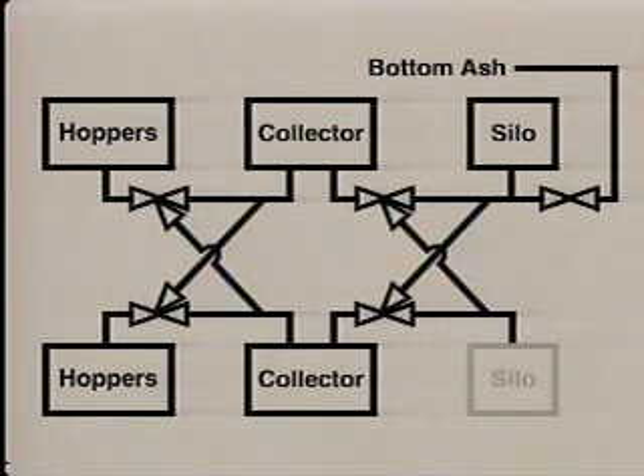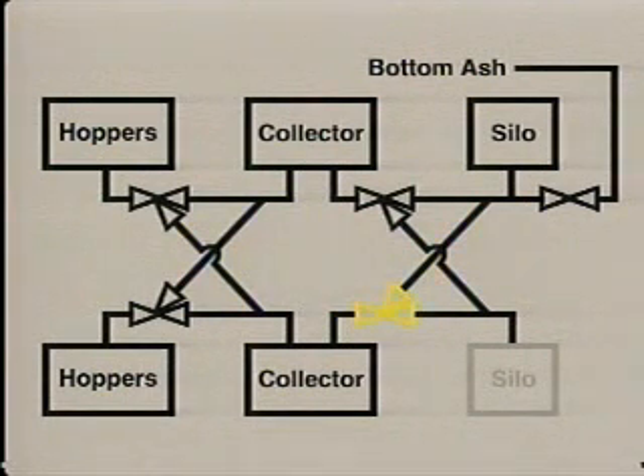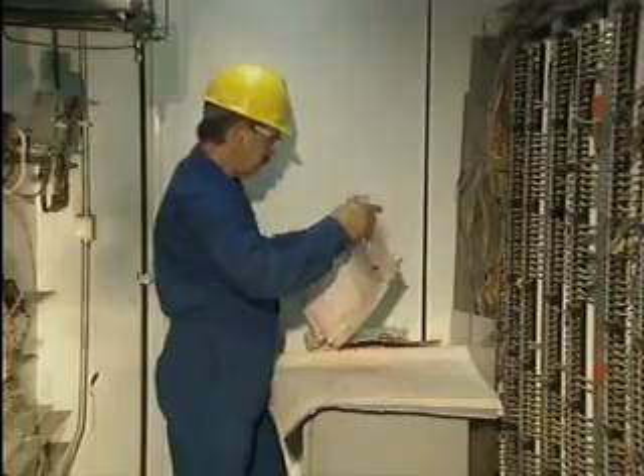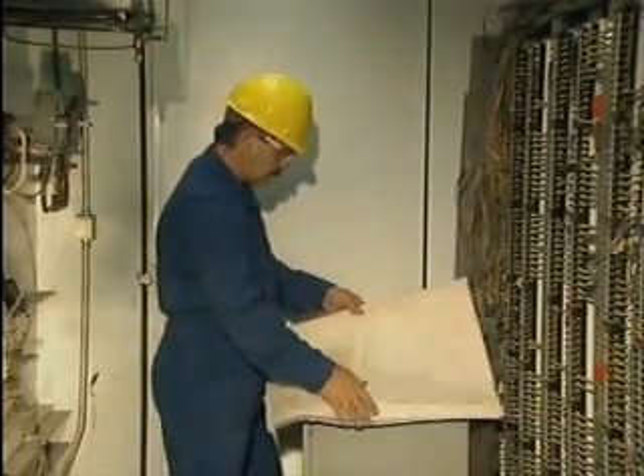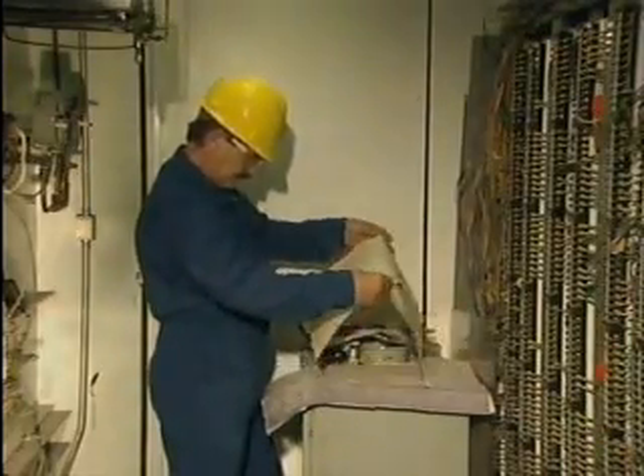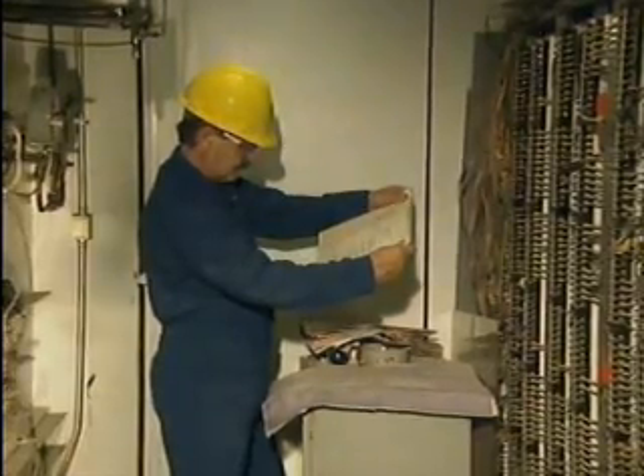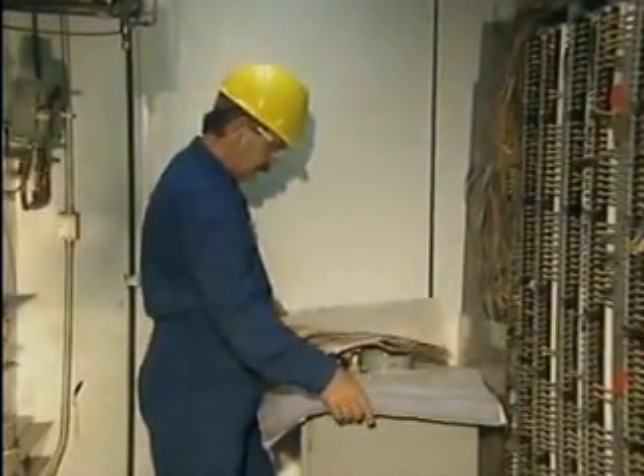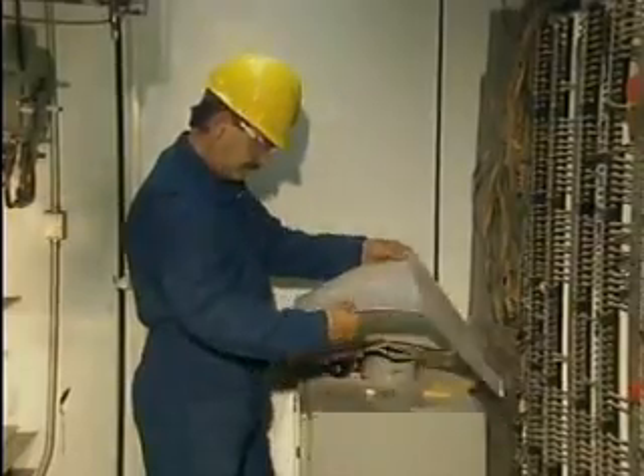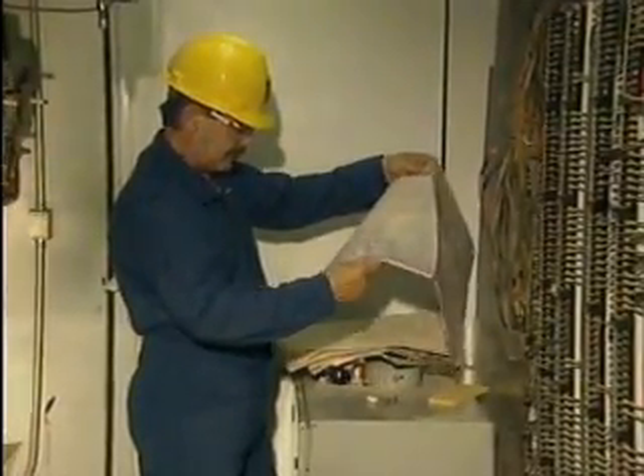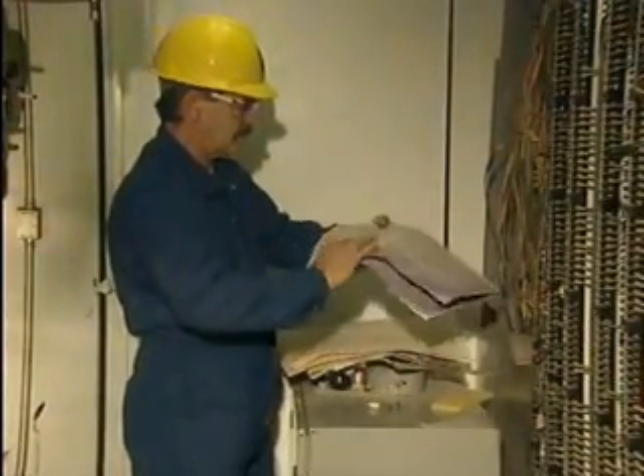Based on this information, the electrician concludes that the problem is located either in the B system silo crossover valve or in the circuitry that controls the valve. The electrician is able to eliminate most of the components in this process because he knows how the process is designed to operate, and he observed the process's control panel indicators. This saved him a lot of time narrowing down the scope of the problem.